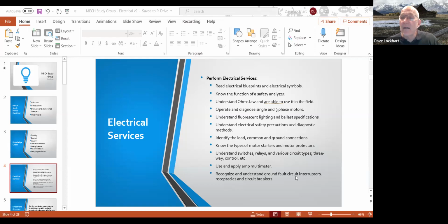And basically that GFCI, it's got a little coil that's measuring what's going through that neutral line in there. So they want your load to be going out on the load side and being consumed and used, and nothing really coming back on the amperage side. So it's measuring any current flowing on that neutral side to make sure it's balanced and appropriate. If not, boom, it instantly trips, meaning that we've got some voltage going to somewhere else, possibly water or other things. So you can maybe study up on understanding what GFCIs do and why we have those.